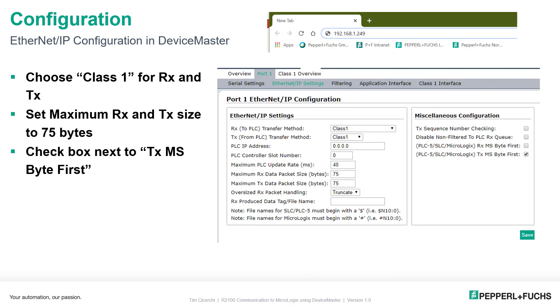When doing the configuration for Ethernet IP for the Device Master, I go to the port 1 Ethernet IP settings tab. Because I'm using a CompactLogix, I find it easy to use Class 1 messaging, so that's what I've selected for both RX and TX. The PLC IP address doesn't matter because we're connecting from the PLC side. I set 75 bytes — just a number larger than the 50 bytes we know is coming in from the Device Master. I'm also going to check the box TX MS Byte first, which reverses the bytes of the distance and quality so they come in in the right order for the PLC.